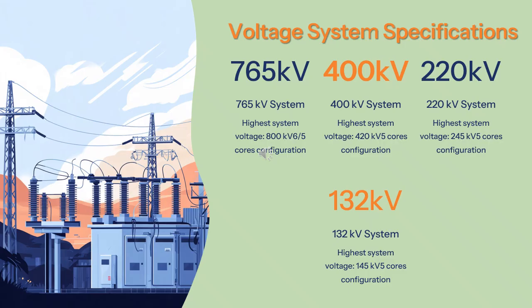Voltage system specifications of the EHV CT: 765 kV, 400 kV, 220 kV. In 765 kV system, highest system voltage is 800 kV, 6 by 5 cores configuration. In 400 kV system, highest system voltage 420 kV, 5 cores configuration. In 220 kV system, highest system voltage is 245 kV, 5 cores configuration. In 132 kV system, highest system voltage 145 kV, 5 cores configuration.